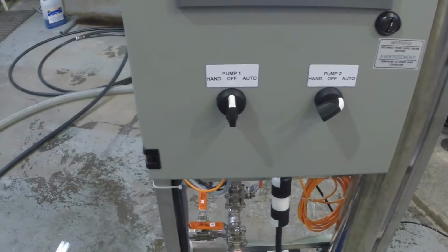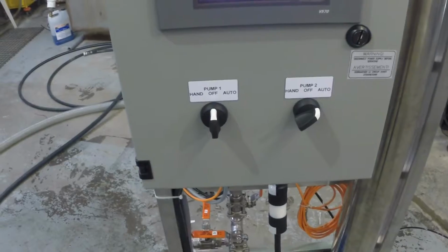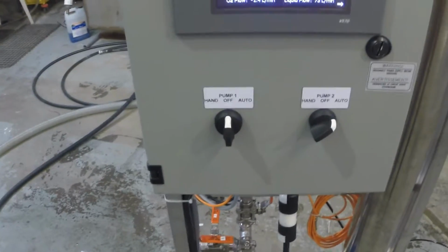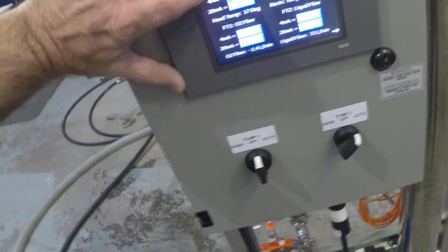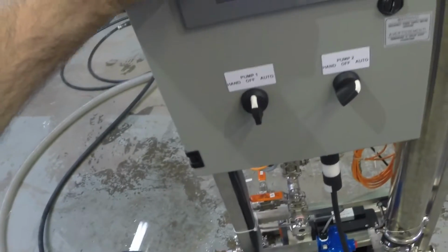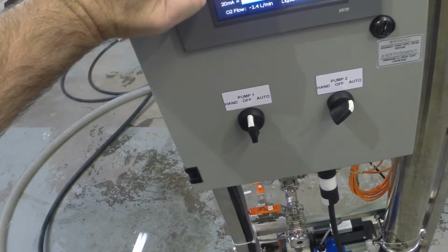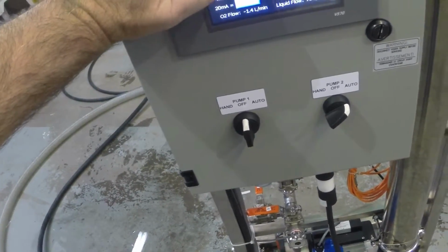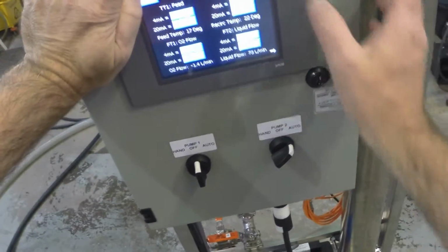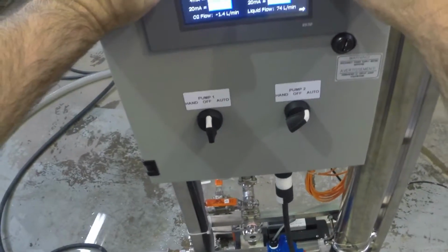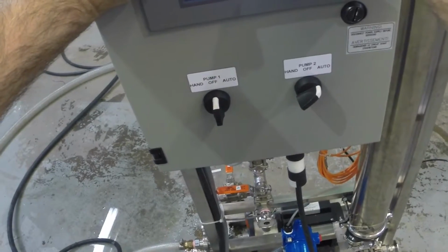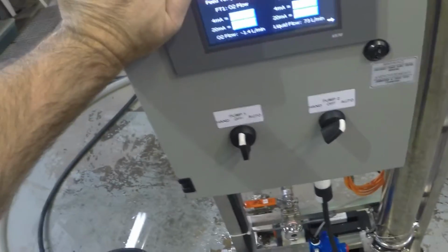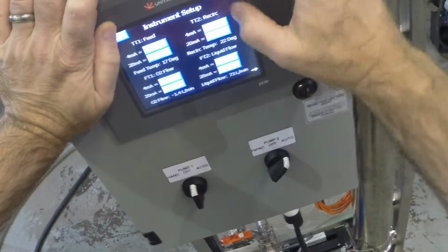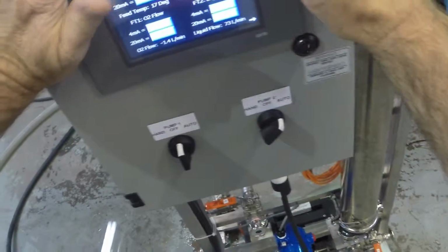These are your set points for calibration of the units. So 4 milliamps is referenced to 0 degrees. 20 milliamps is referenced to 100 degrees. Same with the T2, 0 degrees and 100 degrees. That's the range that those sensors will operate in. So that's just for calibration, so you should never have to touch that.